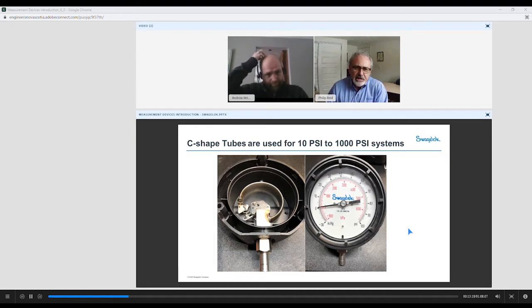Let's take a closer look now at what that really looks like. Going from the party horn back to the inside of a pressure gauge, there are a few things that I will point out here. This has a tube adapter connection, so you can face this gauge any direction you want and tighten it, as opposed to an NPT thread where you're trying to get it positioned and get the thread in the right engagement. Pressure enters.